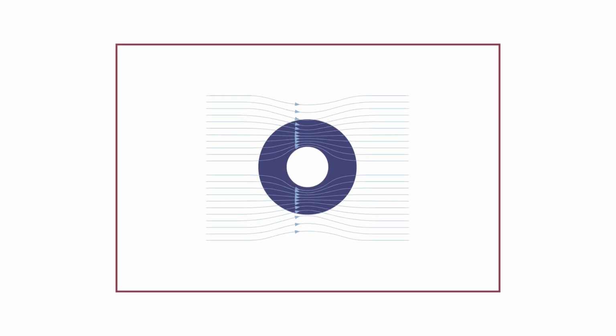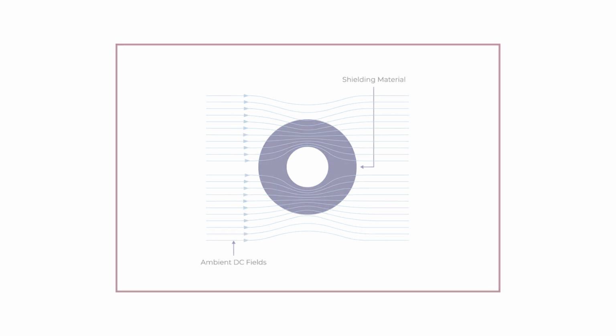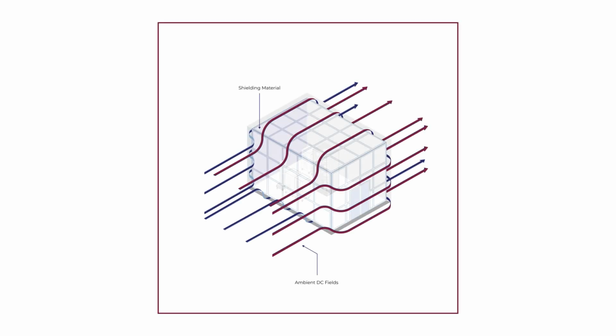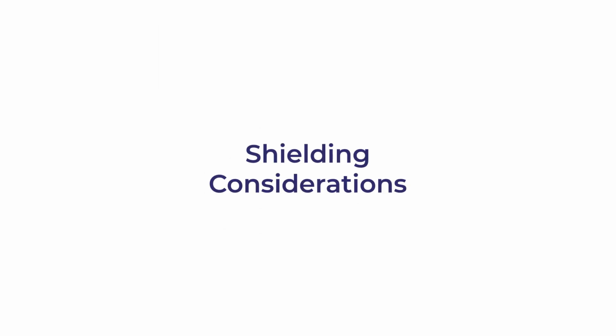The second type of shielding, the flux shunting, uses a highly permeable material like mu metal. Basically, it creates an envelope around the lab that the magnetic fields then follow and do not enter the lab. Because the shielding is a highly permeable material, the magnetic field lines basically follow the permeability of the material shielding the labs and do not enter the labs and do not interfere with the microscope performance. Shielding does work and provides either AC shielding or DC and AC shielding, but there are some drawbacks when it comes to shielding.